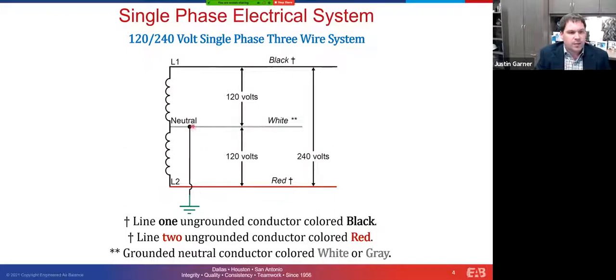And then your neutral is considered by the National Electrical Code to still be a conductor, but it's a grounded conductor. And that means that it's tied to ground at its source, typically at the service entrance to your facility or to your home. And so between the ungrounded conductors and the grounded conductor, you're going to have a voltage potential of 120 volts. And so that's how these systems are derived. And that's what you would notice, like I said, in most residential applications.